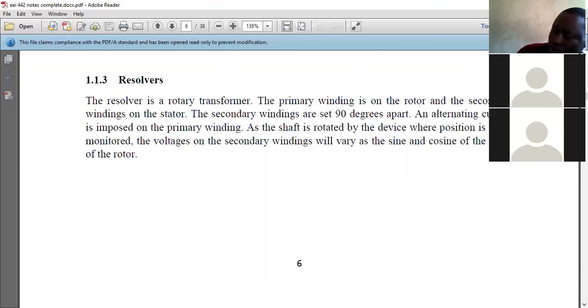So as the shaft is rotated, what happens? When the shaft is rotated, it's able to capture the position of what is being measured, because the voltages on the secondary coil will vary as sine or cosine of the angle of the rotor. So whatever you get will depend on the position of what you are measuring, which determines the voltage produced at the output of the transformer.